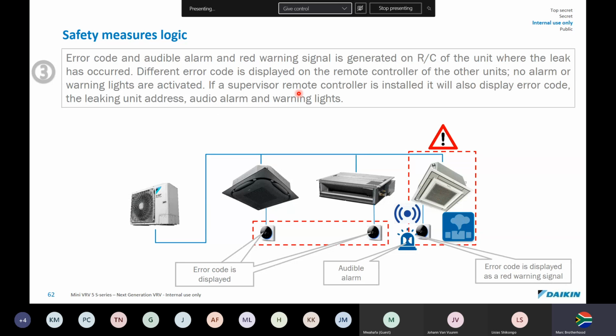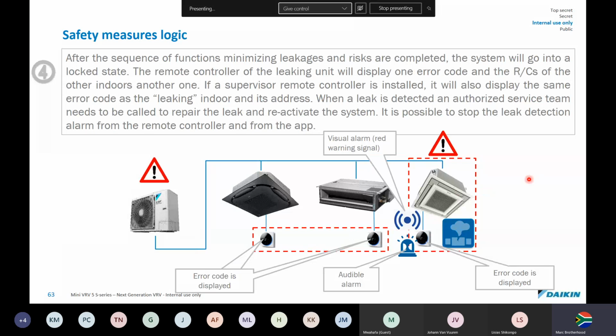If a supervisor's remote control is installed, it will also display the error code with the leaking unit's address, as well as audio alarm and warning lights. And remember, the supervisor can't switch off and disable the alarm. It has to be investigated. After the sequence of functions minimizing leaks and risks has been completed, the system will go into a locked state. So it'll lock out.